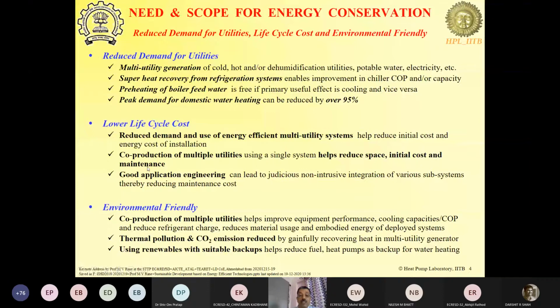In fact, by recovering superheat from this, you are reducing the condenser load, and by reducing the condenser load, your condensing pressure goes down, and by reducing the condensing pressure, the compressor operates at a more environment friendly, means reduced pressure ratio. It is less stressful for the compressor to operate under those conditions, and because of that, what happens is your maintenance requirement on the compressor, failure of the compressor also goes down.